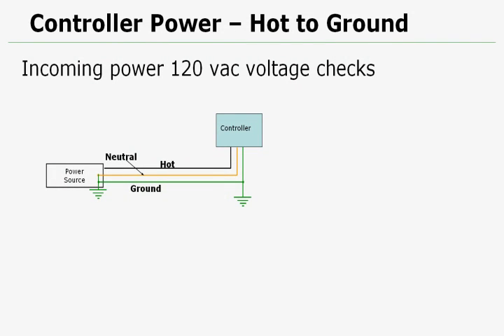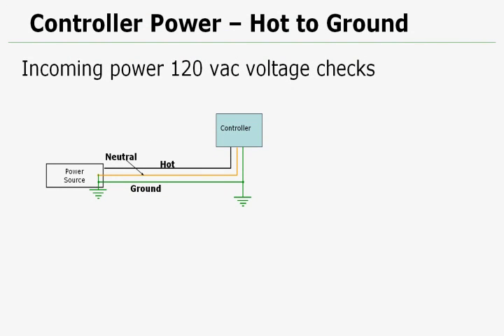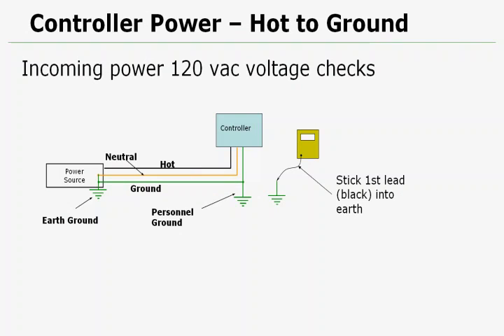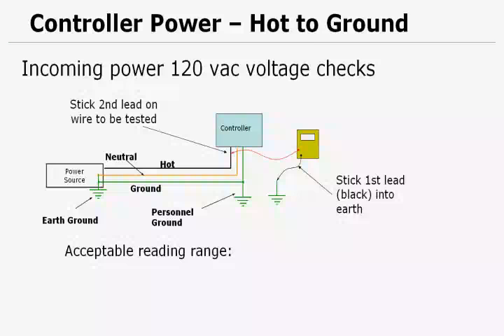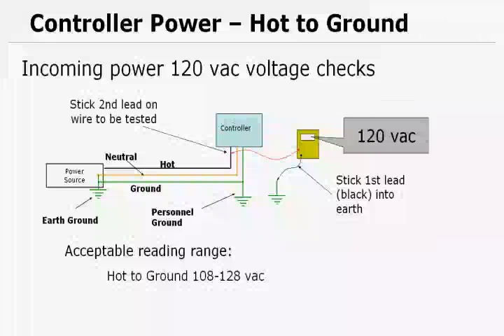So if we have a controller, and we want to read the power readings from hot to ground, looking at our diagram, we have the hot wire black, the ground wire green, the neutral wire in the middle is gold. And then our earth grounds are at our power source. We also have a personal ground which is at the controller, nothing more than a ground rod. Let's take the first lead and put it into the ground. Let's take the second lead and put it on to the hot, because we're reading the hot to ground reading. We should be in a range of 108 to 128 volts AC for the controller to be working correctly.